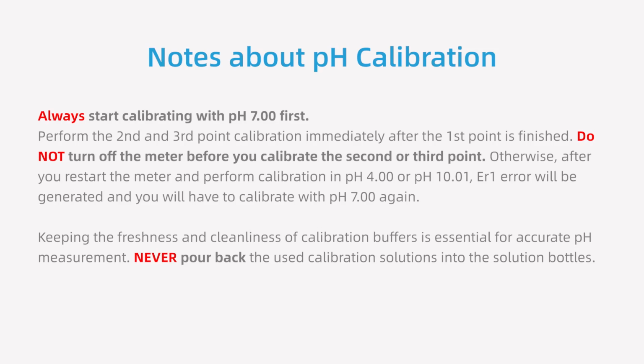Notes about pH calibration. Always start calibrating with pH 7.00 first. Perform the second and third point calibration immediately after the first point is finished. Do not turn off the meter before you calibrate the second or third point. Otherwise, after you restart the meter and perform calibration in pH 4.00 or pH 10.01, Er1 error will be generated and you will have to calibrate with pH 7.00 again.